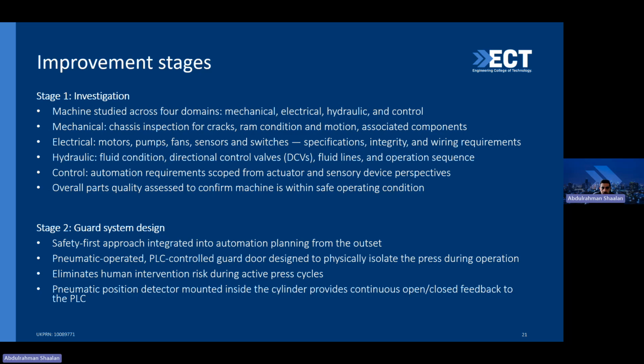Electrically, we looked at the motors, pumps, fans, sensors, and switches that the press had. Hydraulic-wise, we looked into the hydraulic fluid condition, or the oil condition, the directional control valves, operations and conditions, all the different lines and connections, and the operation sequences. From the control side, we looked into what it requires in order to transform this machine from the very basic relay logic into PLC.